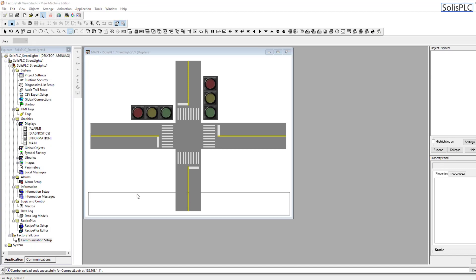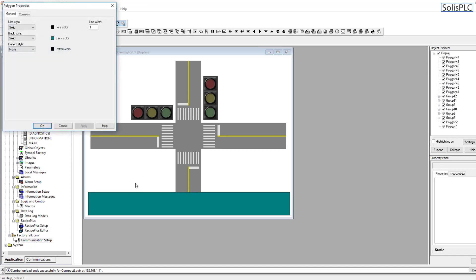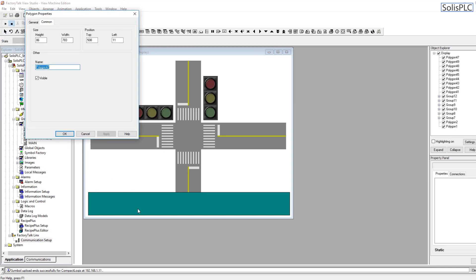It's considered good practice to control the HMI from a separate screen — essentially a pop-up — rather than from the main overview screen. One reason is that you might want to enable security features such as user login so that certain users can't make changes. Today we're just going to implement the buttons without focusing on security, but the control screen will still be separated so you can't inadvertently click on things without navigating to that specific screen.